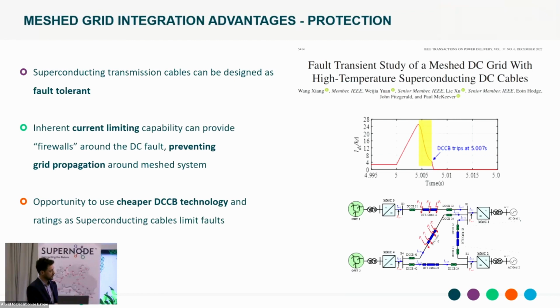I'm pointing at the image on the right, the graph. When a fault occurs on the grid, we can see that before the DC circuit breaker even needs to open, the cable itself has acted to quench the fault and reduce the fault current level. And that's very useful, so we can leverage that in how we approach design and development of DC circuit breakers. In a mesh grid situation, this inherent capability of the cable can be used to act as a firewall to stop propagation of faults around mesh DC grids. So that's really, really useful.